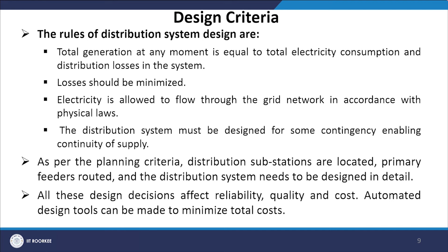The major criteria and rules for distribution system design are: total generation at any moment must equal total electricity consumption plus distribution losses; losses should be minimized; electricity flows through the grid in accordance with physical laws; and the distribution system must be designed for contingency to enable continuity of supply. It is better to have at least N-1 contingency for substation transformers and main feeders. Design decisions on substation location, primary feeder routing and system layout all affect reliability, quality and cost. Automated design tools can help minimize total cost.